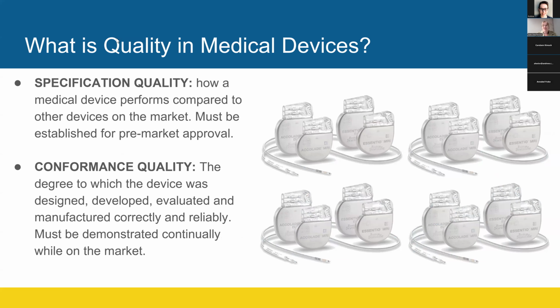So we actually have both of those in medical device. There is what we call specification quality, which is how a medical device performs compared to other devices on the market. If you've heard of a 510(k) or a pre-market approval, it's basically saying this is as good as an existing device that had already been approved by the FDA. But we also have what's called conformance quality, which is how closely that device was designed, developed, evaluated, and manufactured correctly and reliably.